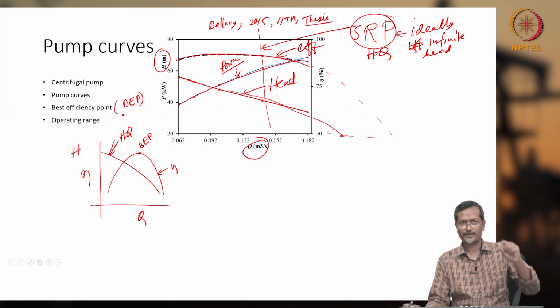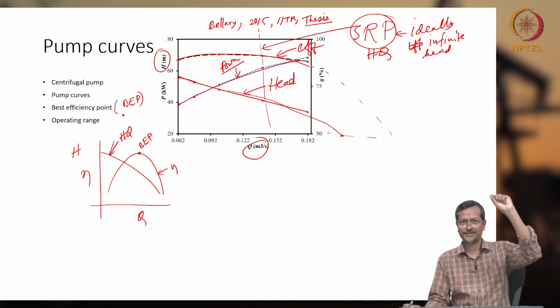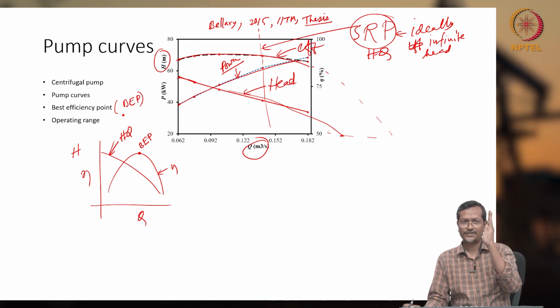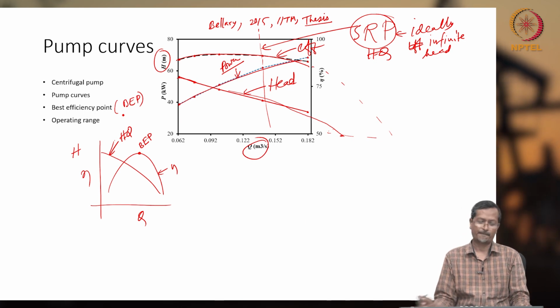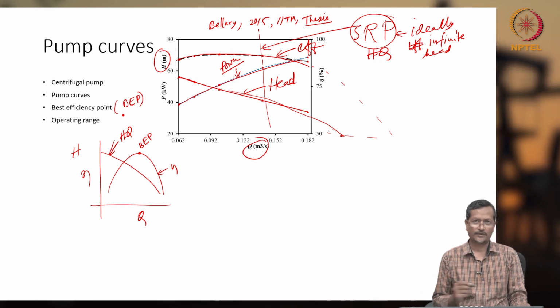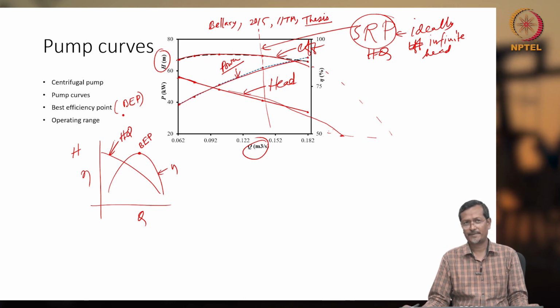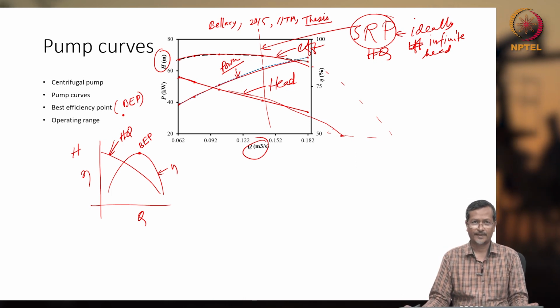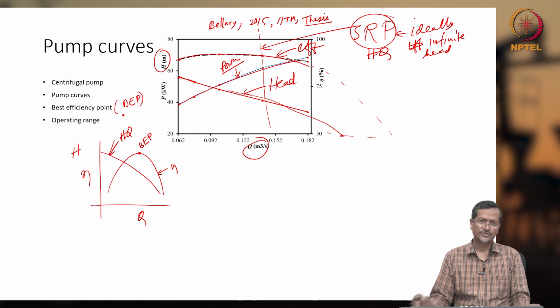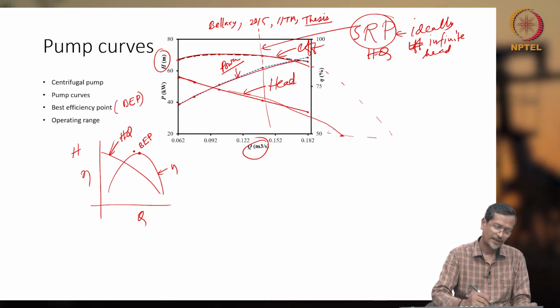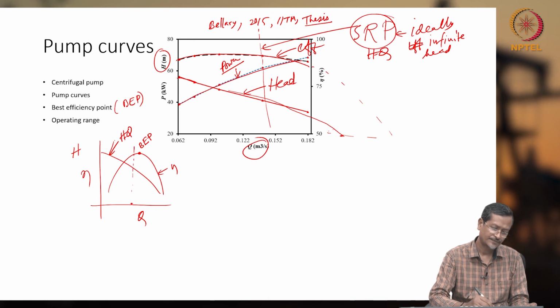Okay, best efficiency point means where you are getting very high efficiency, and if you change the flow rate a little bit left or right, your efficiency goes down, you can see. Okay. So, running your centrifugal pump at BEP is very difficult, because there will be so many variabilities like a restriction here and there, friction. So, what the pump design will be suggesting, you run within a certain range, plus minus 10% of this BEP.